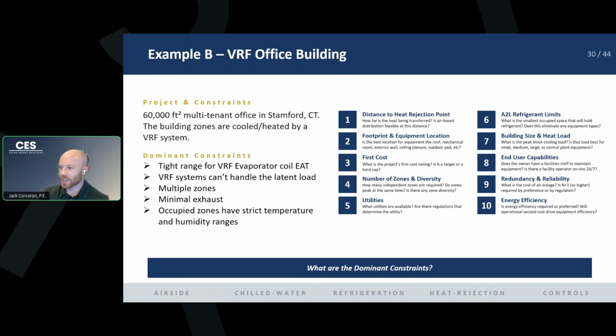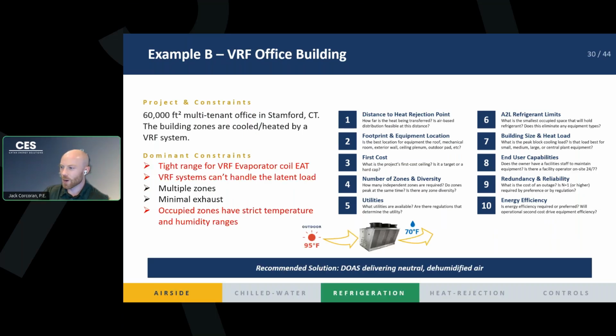And each of these zones has a tight temperature and humidity. It's an office space, right? You can't have people in a clammy, wet, cold environment or very warm or dry space, right? You want to be comfortable. So what type of outside air system do we want to use? We're going to do a DOAS system, right? And so that is driven entirely by the VRF system, right? You're going to need an outside air system that can get rid of the latent load before it reaches the VRF coil. So whenever you hear VRF, you're pretty much going to need to have a DOAS system.